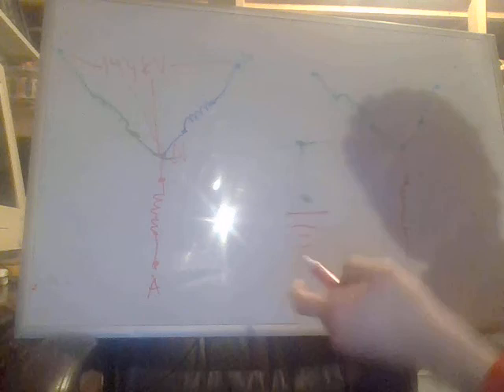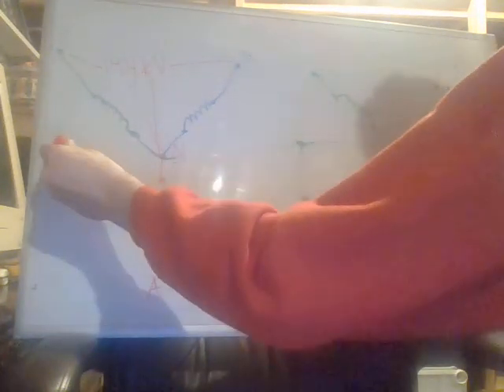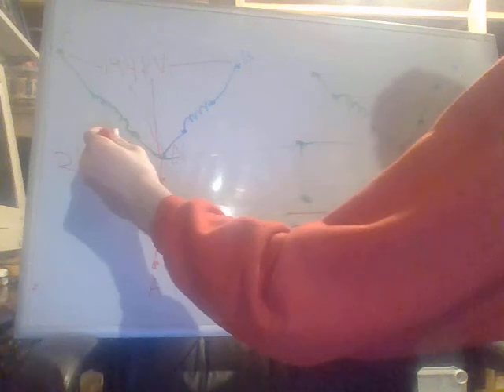Alright, so again, we have a phase voltage on the primary side of 14.4 between any of these and neutral. So 14 kilovolts here to here, or here to here, or here to here. But when we go across two windings, line voltage is 24.9.